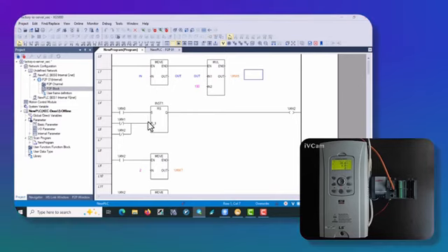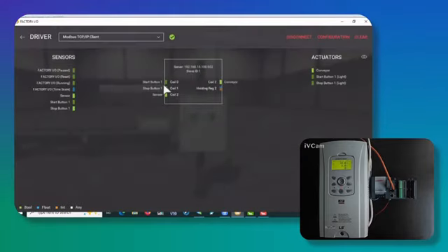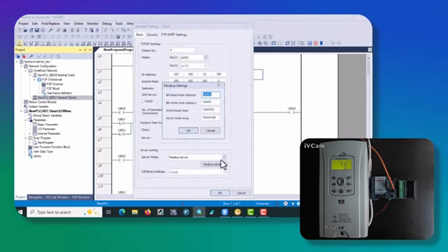Over there in the factory I/O software, I had a start, a stop, and also a sensor. Now if I enter the driver here, you can see that my coil 0 is the start, address 1 is the stop, and address 2 is the sensor. In the software as well, we've specified that in the FENet section, in our Modbus map, the address related to the bit write area starts from MX0. That means my 0 address becomes my MX0.